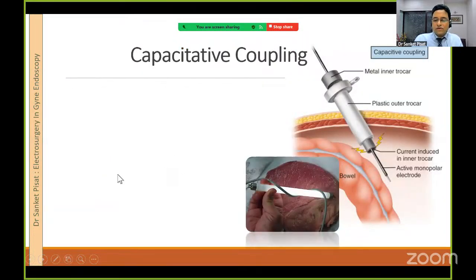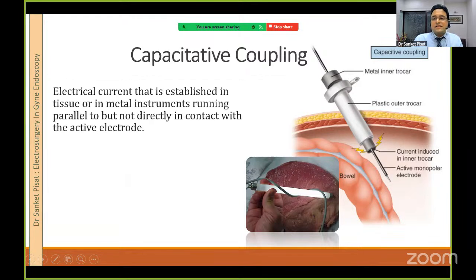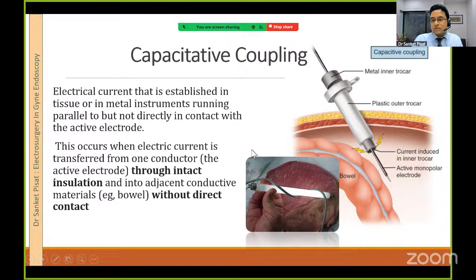Then we come to the second type, which is called capacitive coupling. And what is capacitive coupling? Current that is established in tissue or in metal instruments running parallel to but not directly in contact with the active electrode. Imagine a clinical scenario. This is the monopolar electrode, and you have got another metallic instrument covering this, like a metallic reducer or a metal inner trocar. What will happen as the current flows? It is like activating the external metallic instrument by way of current passing through the center of that instrument. So electric current is transferred from one conductor through intact insulation to adjacent conductive materials without direct contact.